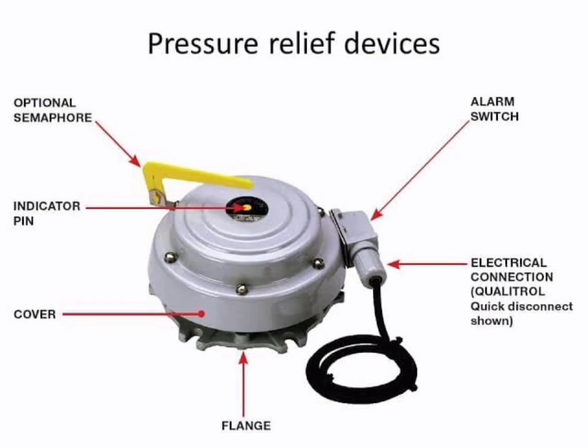A pressure relief valve (PRV) is a type of protection device used to protect transformers from damage caused by excessive pressure. The pressure inside a transformer can increase due to a variety of factors, such as a fault, a change in load, or a change in oil temperature. The PRV is typically installed on the transformer's conservator tank and is designed to detect changes in the pressure inside the tank and respond by releasing the excess pressure to the atmosphere, preventing damage and ensuring safe operation.